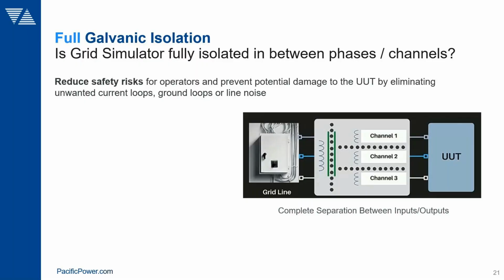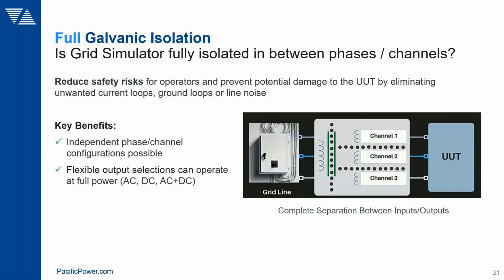Safety is important, and one aspect of that is isolation—having the ability to have isolation between your grid connection, your facility power, and your units under test, as well as individual channel-to-channel isolation. The three output phases, if isolated from each other, can be at different potentials. So if used as three separate outputs, they can float at different levels without a common neutral, which can be very effective in complex test setups. Doing that in a facility gives you more operation and power capabilities, and eliminates the need for additional external isolation transformers. This is one of the benefits of making the right selection of grid simulators—important aspects to consider.